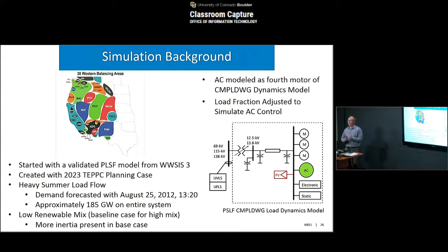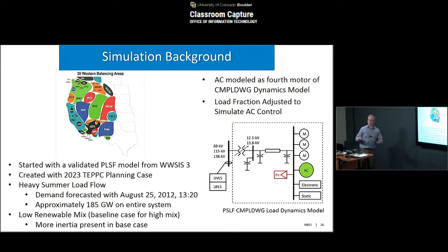So this is the case that everybody plans to. You have to be able to meet load on the hottest day of summer and have a margin. You also need to survive the largest single contingency, which is that Palo Verde nuclear reactor outage. That's happened multiple times. They actually built a double line to Palo Verde, spaced apart, thinking both lines would never go out together. Within a couple months, a helicopter ran into both lines, and it tripped out. So this is a credible contingency.